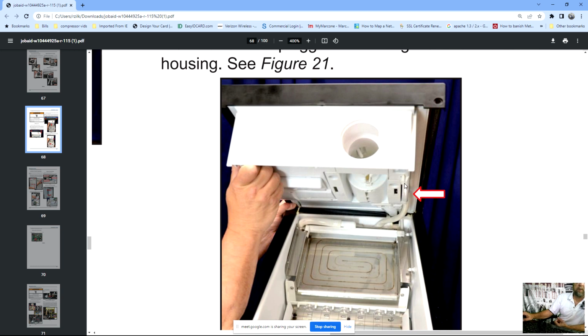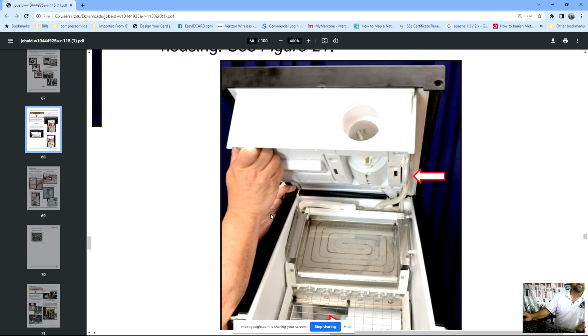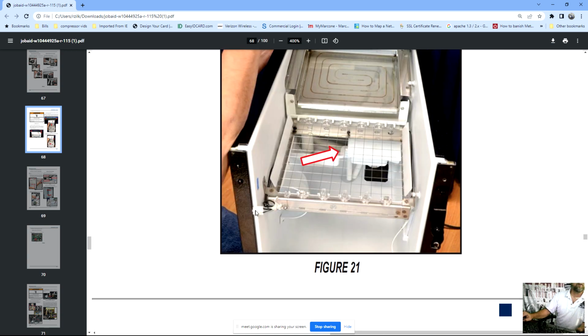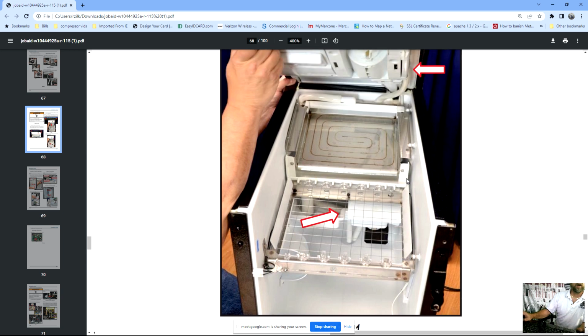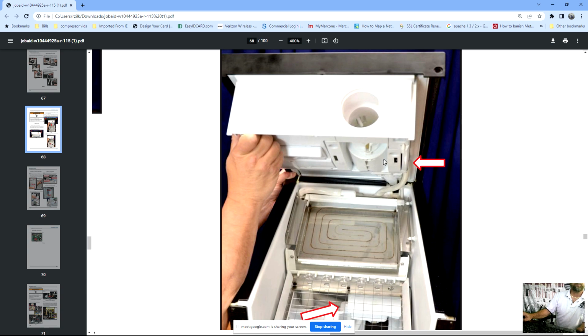Now there is an evaporator thermistor on this unit. It might be plugged in behind this wire harness here. I cannot see it, but there is one other connector that's inside of this unit. So in order to get into the computer controls, you have to lift up the top like this, and you'll have to disconnect the three plugs. One where the guy's hand is, that goes to the cutter grid here. This is the wire to the bin level sensor, and there should be a third wire, which I don't see, which plugs into the board. It's our evaporator thermistor.